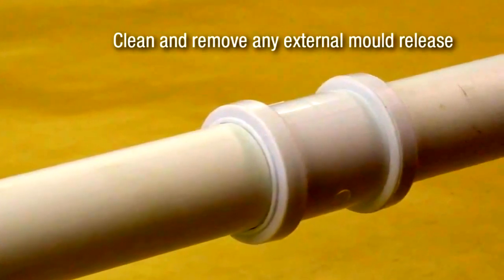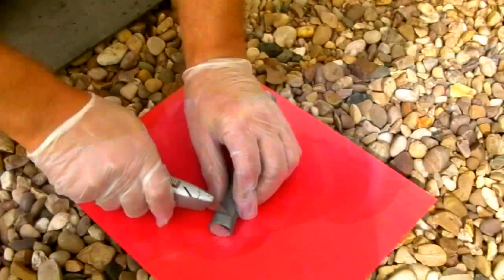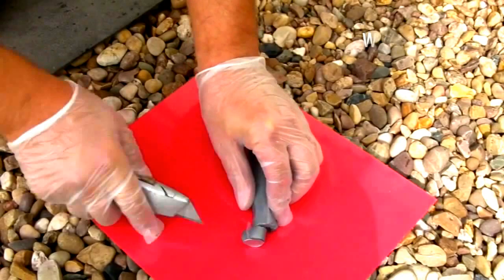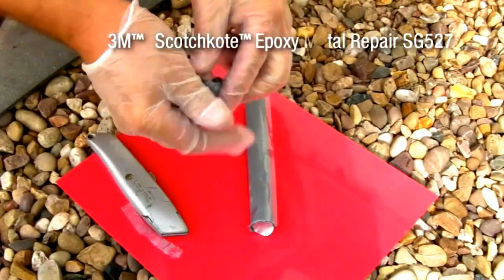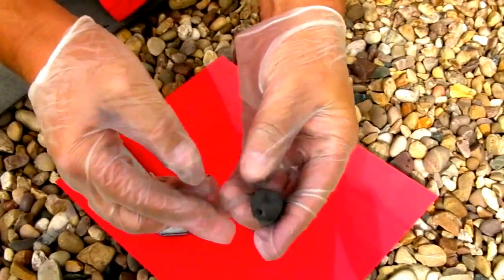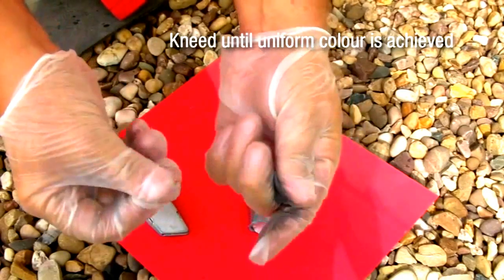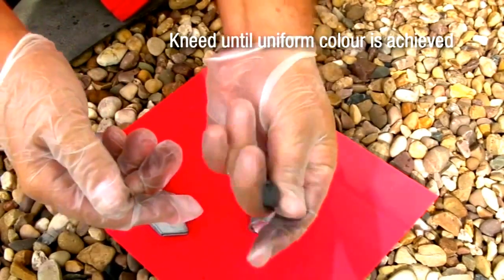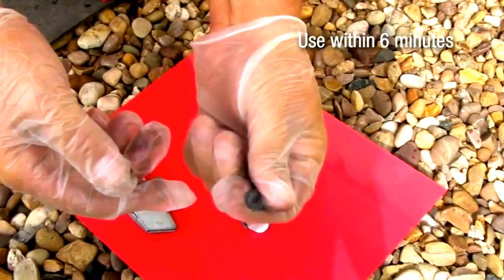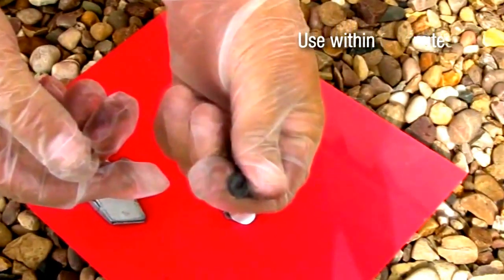Wearing gloves, begin to prepare the 3M Scotchkote materials. Cut the required amount of Epoxy Metal Repair SG527 and knead until a uniform colour is achieved. The two components are in a single stick and are colour coded — complete mixing is achieved when the colour is uniform. SG527 should be used within 6 minutes of mixing at 20 degrees centigrade.